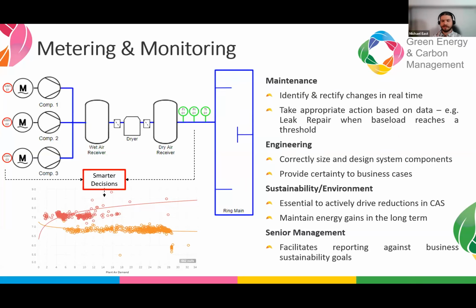It also lets your engineering team make proactive, informed decisions about the compressor, dryer, piping, and air receiver sizing, and then have certainty around the business case when they put that up for CapEx or modifications, getting away from that reactive approach of 'let's just do a like for like replacement because we've run out of time, but let's make sure it's got a VSD on it.' So you can make better decisions with plenty of time up your sleeve. Then when we get to the sustainability and environment managers, having that metering in place is essential to unlocking what opportunities are available that are unique to this site and this compressed air system.